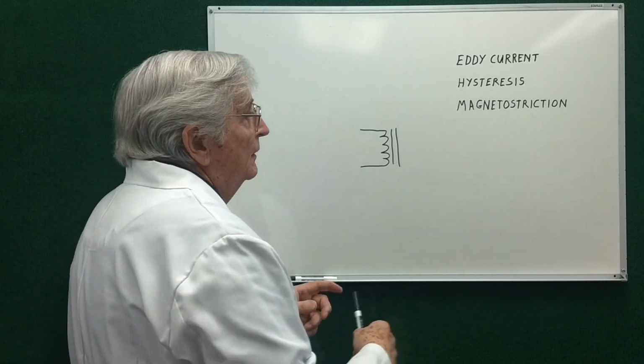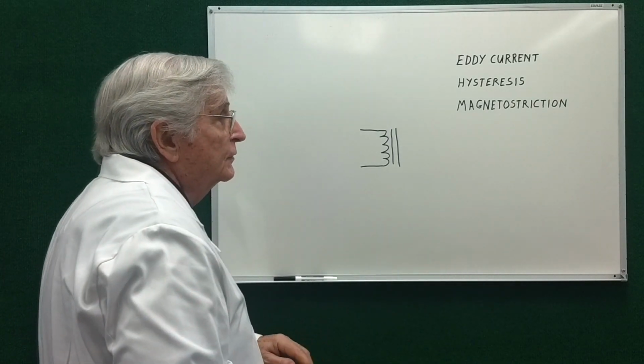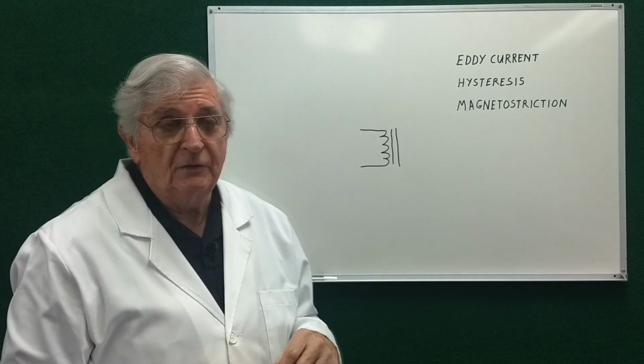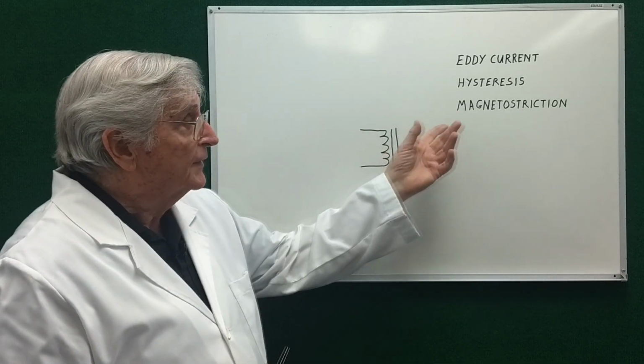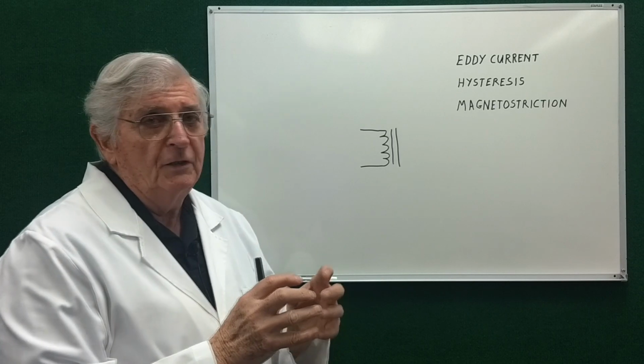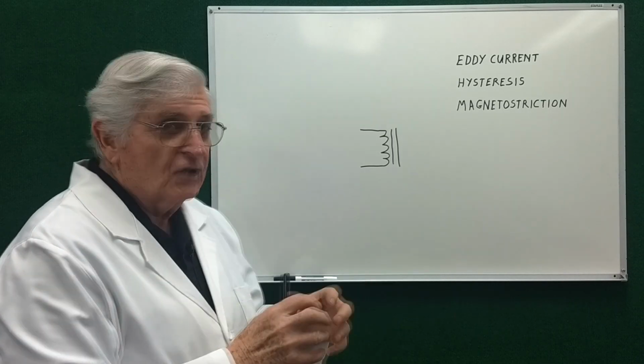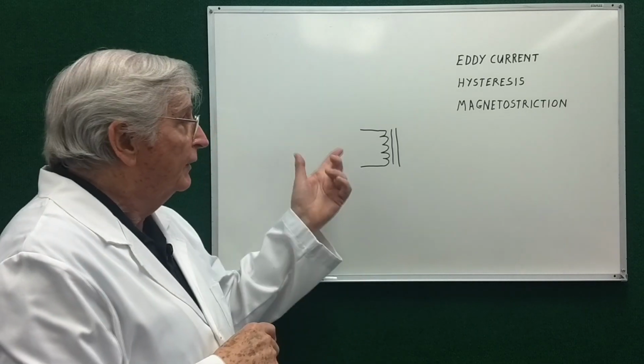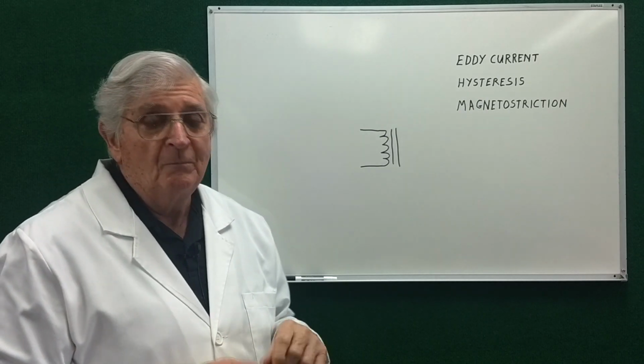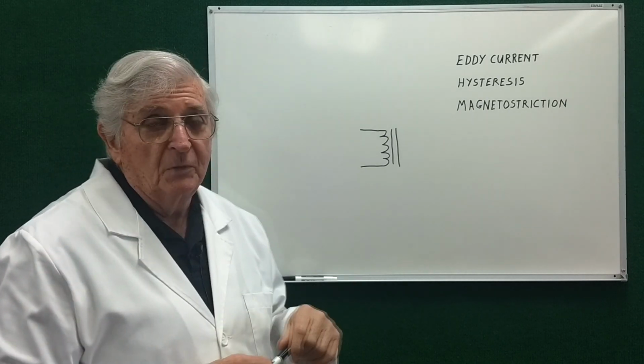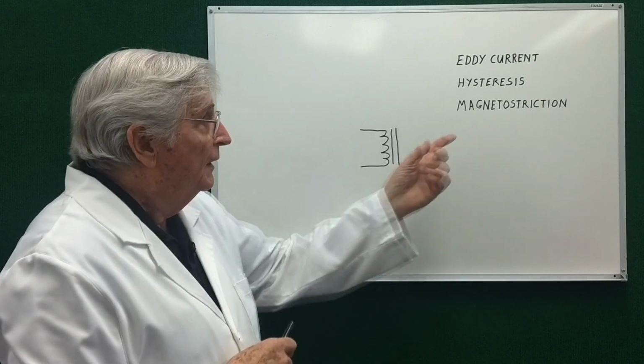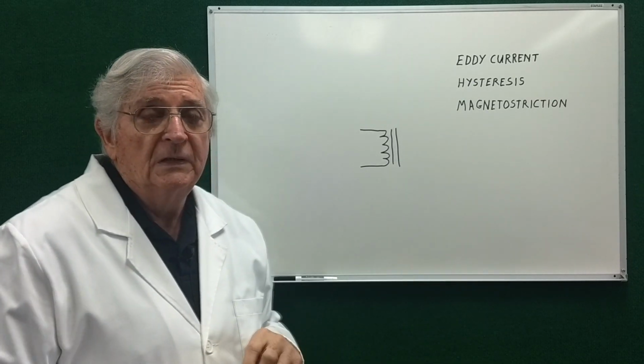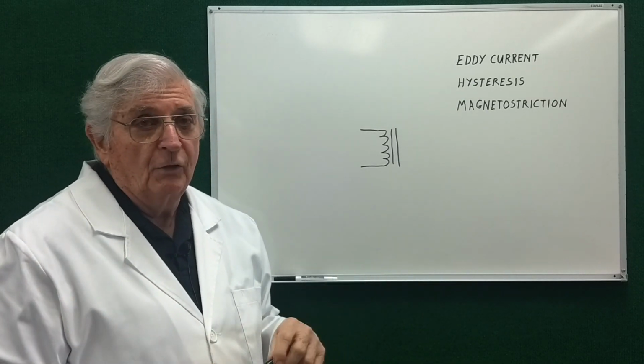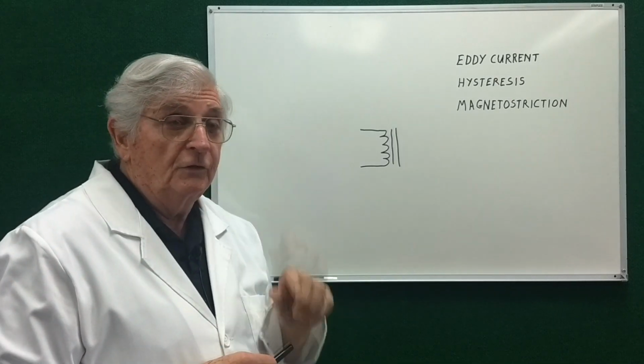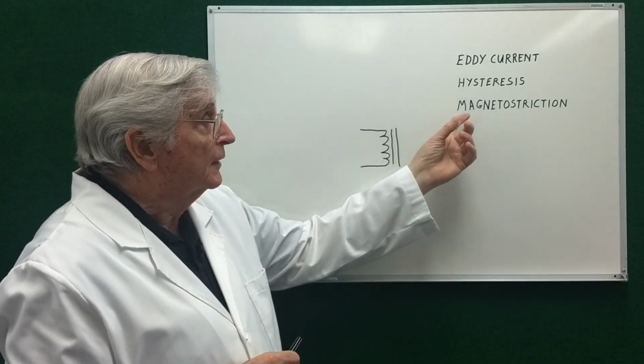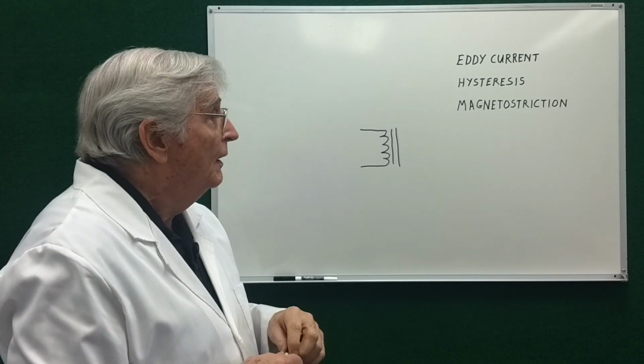And the third type of loss is called magnetostriction, and that's a case where the actual volume of the core changes with the amount of flux going through it. Now, for small transformers like we're talking about, this isn't very important, but in large power transformers, power distribution transformers, that can be a major factor.